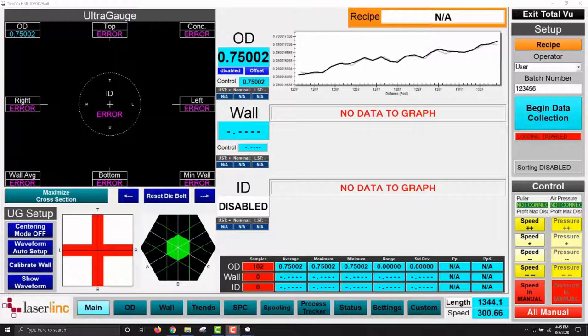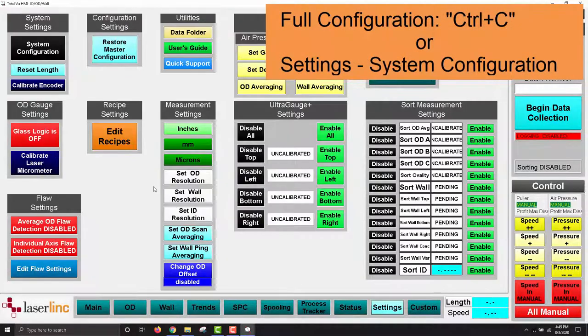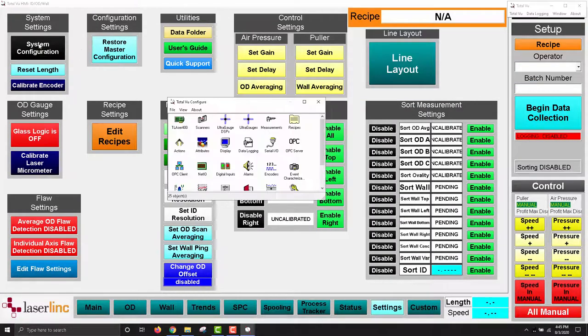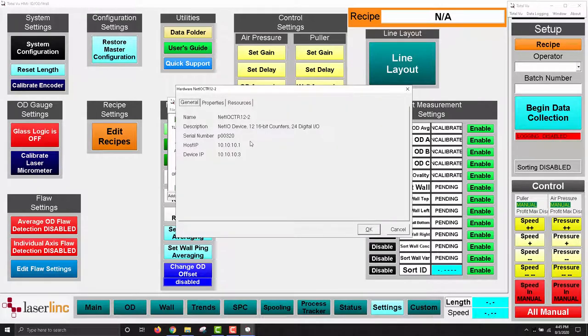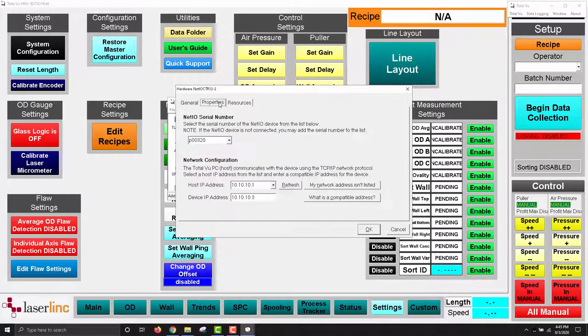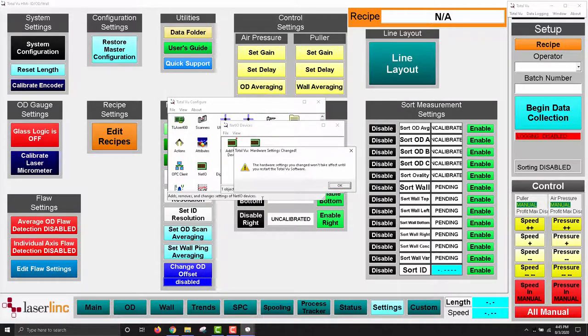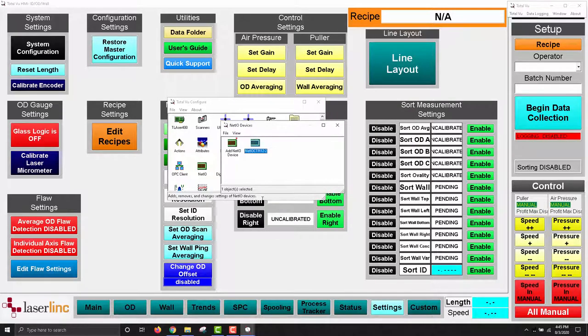Next, we'll check the NetIO. Press Ctrl-O to open the full configuration menu and click on the NetIO icon. Then click on the predefined NetIO device. Again, verify that the serial number and host IP address are correct. Check that the device IP address is compatible with the computer's network and that it is not assigned the same IP address as the gauge. Once complete, press OK. If any changes were made, TotalView will ask to restart.